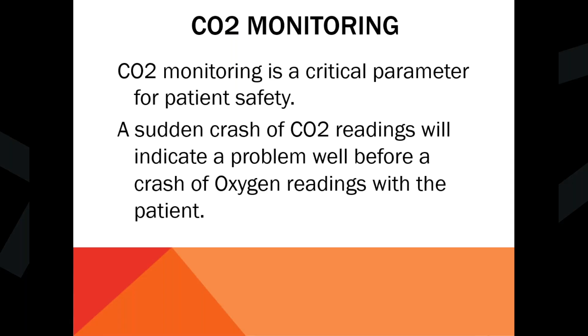And then here's my lovely daughter with a CO2 module that she was having some issues with. One thing to keep in mind is that these have a water trap in them, and if the water trap gets full, then it won't let the CO2 through. So if you get called on a CO2 module up in the OR and they're saying, I can't get my CO2 readings, you can ask them on the phone, hey, have you changed the trap on it? And if that doesn't work for you, then call me back, depending on who you're dealing with. But that in a nutshell is basically your CO2 module.